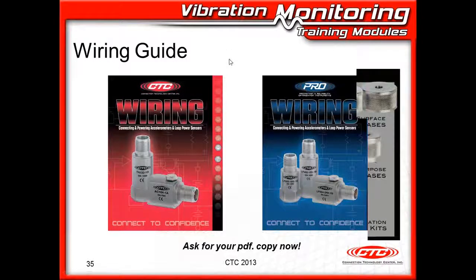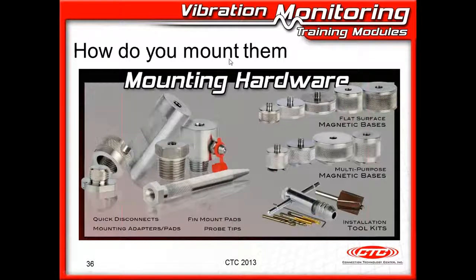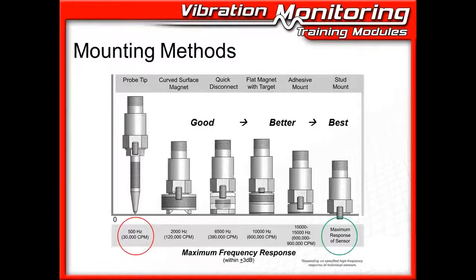All right. We have a really big range of mounting hardware, and I applaud those of you that are drilling and tapping, because that's really the best possible mounting system you have, not only for reliability but also for frequency response, because you've not put anything between the sensor and the machine. And when you look at all these items that are on the screen here, every one of them adds mass and reduces stiffness. When you put one of these between the interface of the sensor and the machine, you're going to change the frequency response. And the trick there is knowing how much.